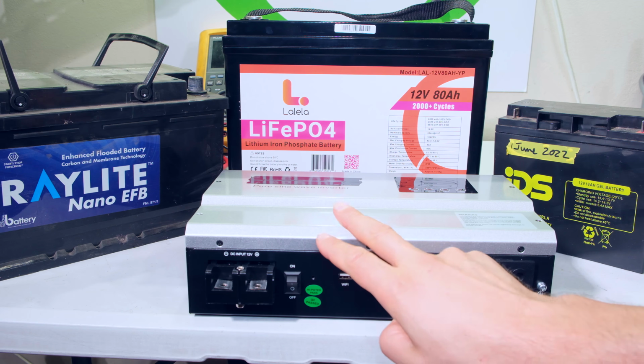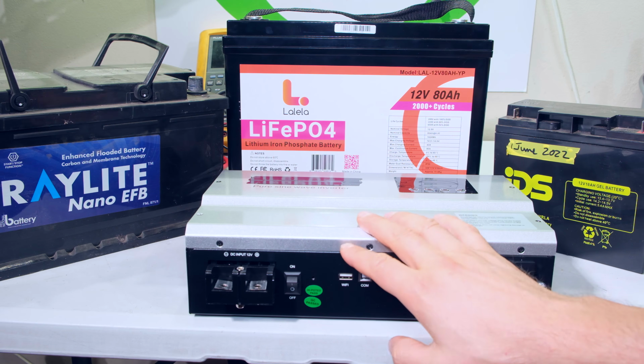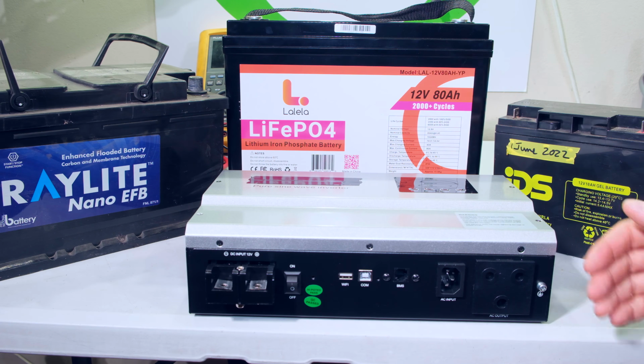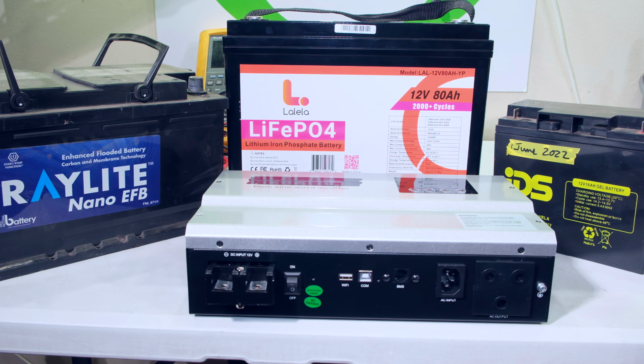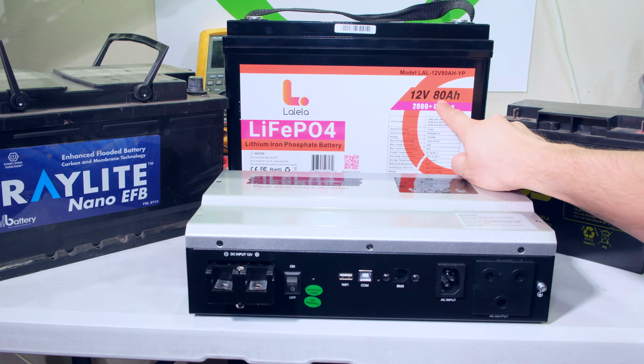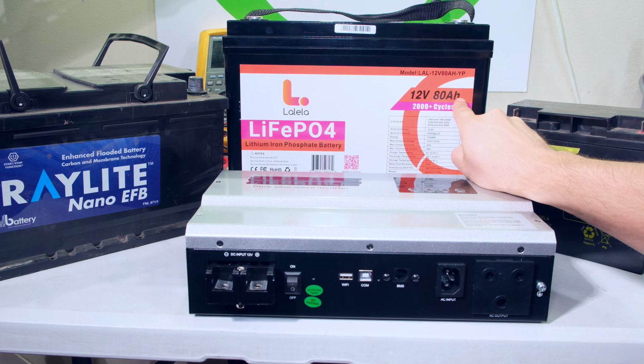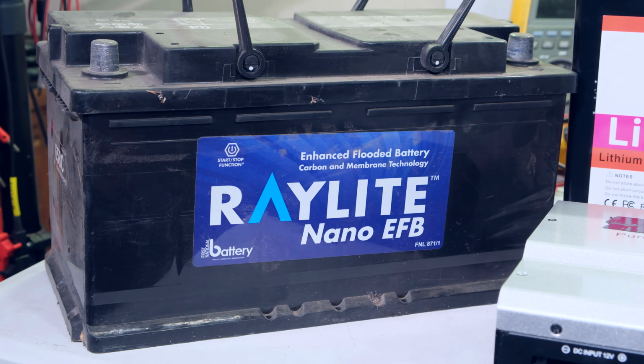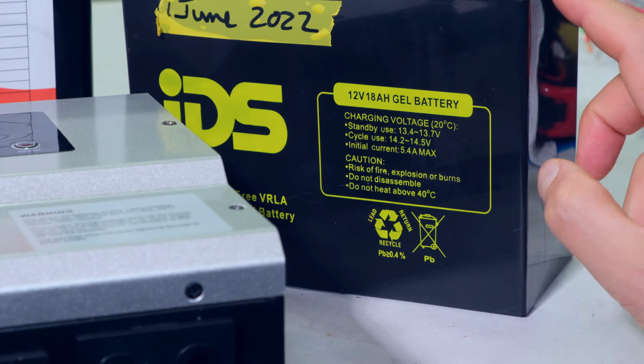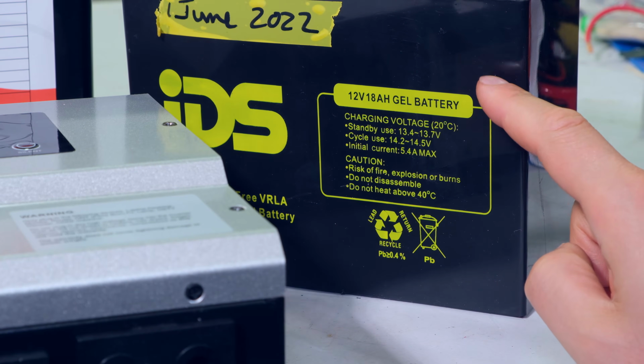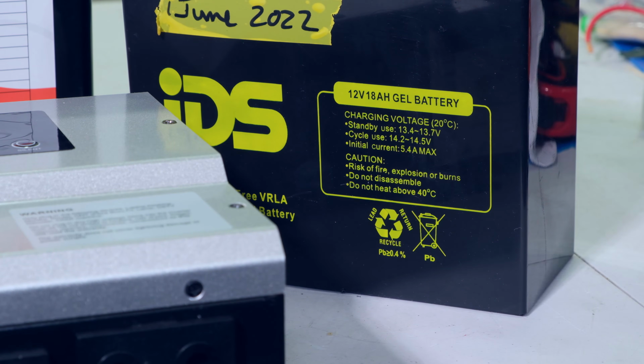Now, if I need a lot of backup time from my inverter, then I need a battery which can power the inverter for a long period of time. Therefore, I would choose a battery that has a high capacity. So the capacity is shown there. In this case, this is 80 amp hours. This car battery is 100 amp hour. This much smaller battery is only 18 amp hour. So that means that if I use a smaller battery, I'm only going to be able to use my inverter for a short period of time.